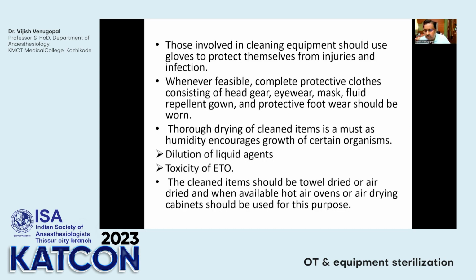Now, those involved in cleaning should take their own precautions to protect themselves from infection. So, whenever feasible, complete protective clothing consisting of headgear, eyewear, mask, fluid repellent gown, and protective footwear should be worn. Now, thorough drying of these cleaned items is a must because humidity encourages the growth of certain organisms. For example, if the instrument has some liquid or water on it and you're going in for a liquid sterilization, there is dilution of the liquid sterilizing agent that you're adding. Suppose you're going for gas sterilization, and for example, you're using ethylene oxide, ETO. ETO will dissolve in the water on the instrument and form a very toxic ethylene glycol, which is very difficult to remove. And it's going to go into the patient and cause problems. So be very careful. Make sure that the cleaned items are towel dried or air dried. And if possible, you can put them in air drying cabinets or even use the hot air oven.